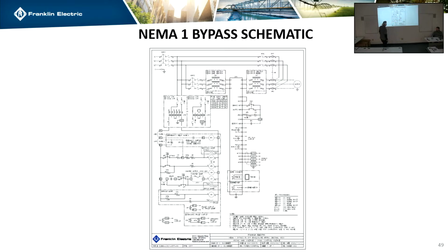And then all of our bypasses are 3 contactor as well. There are other manufacturers, if people want to reach out and ask for a 2 contactor bypass. It's not something we do. We used to offer it, but honestly, we just didn't sell a lot of them. Most people want a 3 contactor because you get that VFD isolation, to be able to troubleshoot the drive by itself without having to take the system offline. Well, it doesn't make sense. Why would you pay for a bypass and then not have it be able to? We never sell 2 contactor. Exactly. Like you're asking for a bypass and you can't run it without the drive. So that's why we're standardizing it. They're all going to be 3 contactor.